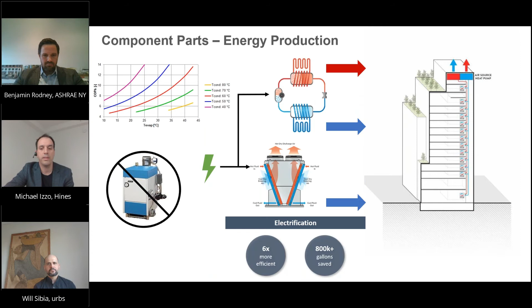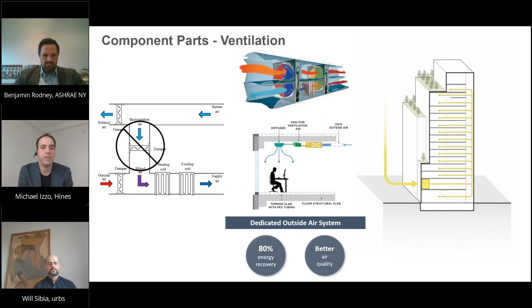On the ventilation side, we chose a DOAS system. We're bringing fresh air, outside air, filtered direct outside air directly to the occupant zone on the floor. We're not sending it into a mixing box or an air handling unit at the mechanical room somewhere. We're eliminating the large recirculation air and delivering fresh outside air to the occupant itself. That allows us also to do 80% energy recovery and also give us better indoor air quality.